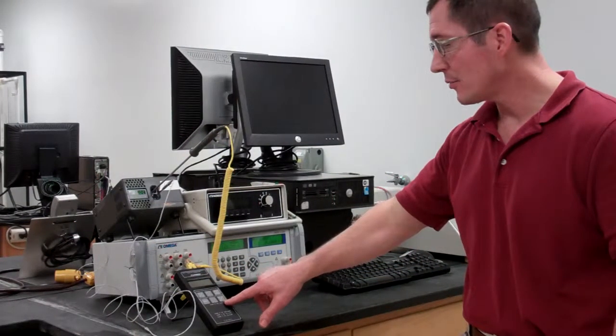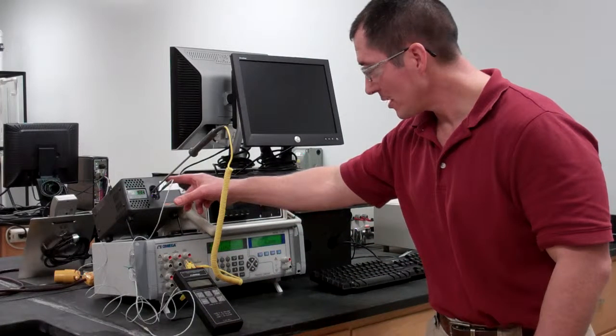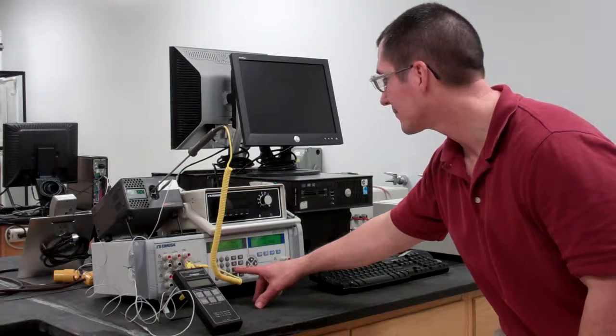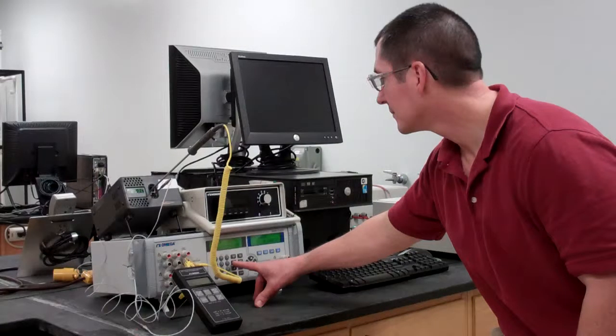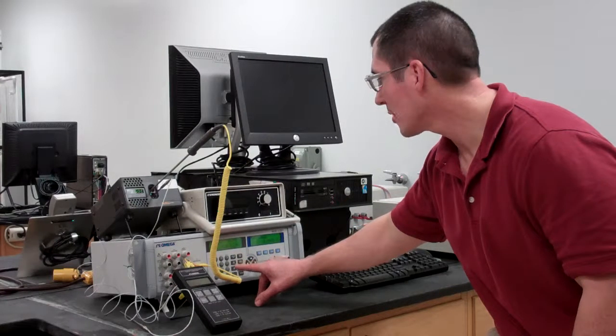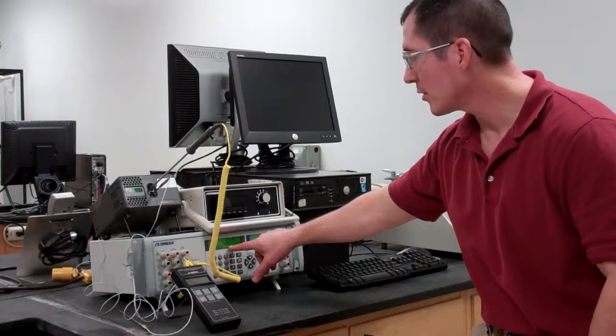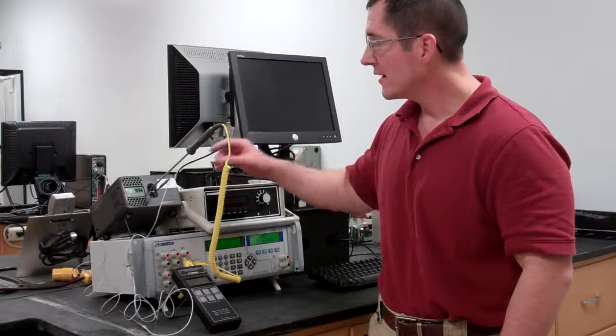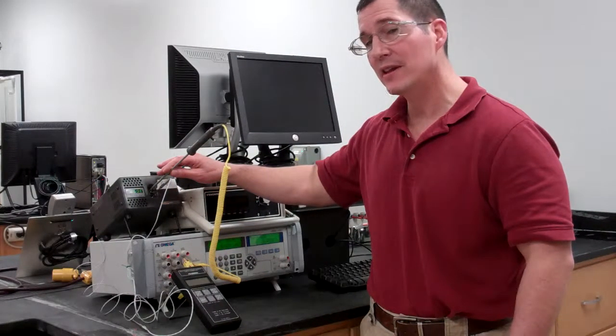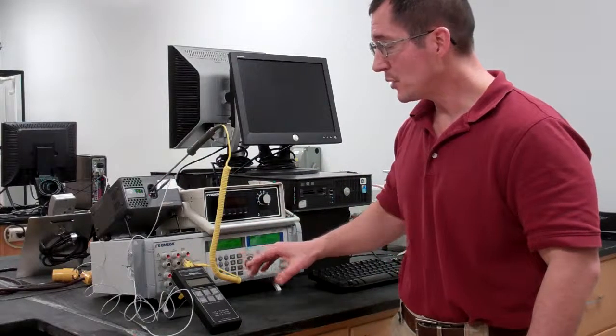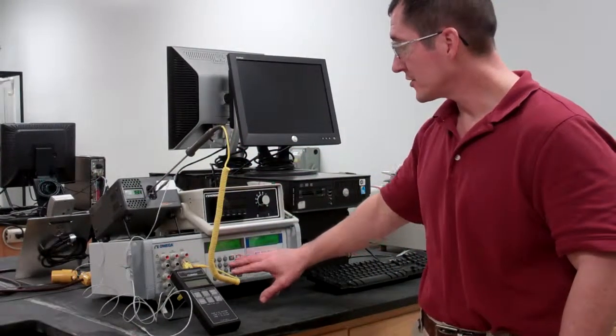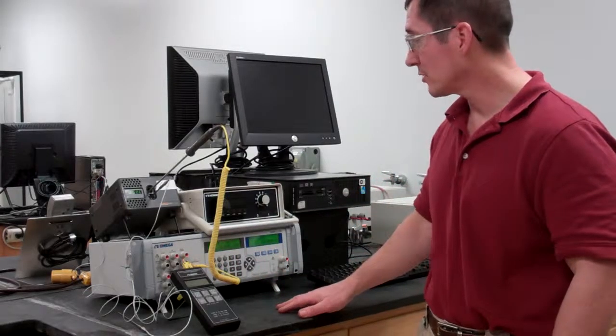Similarly with the thermocouple sensor, I have one in here as well and I can switch to it. So, thermocouple input, and there's my thermocouple reading. I want you to compare the outputs. Of course, the output of the thermocouple is the input to your controller, and in this case, the calibrator is where the signal is going in.